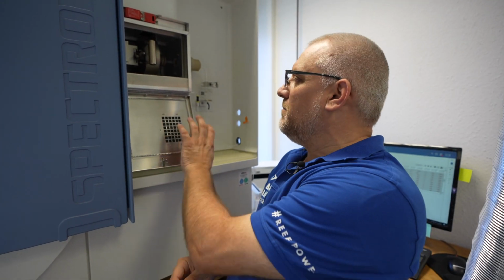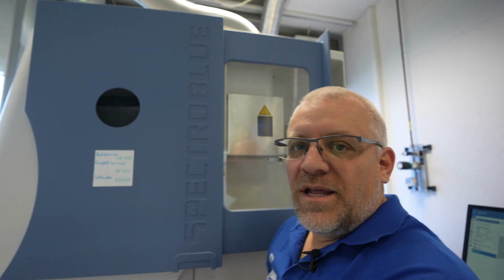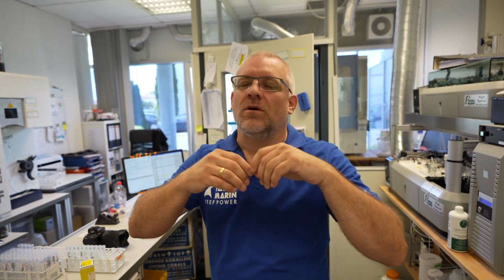The difference on this machine, so we can go to the other one and show the difference there, is that it is way more stable. We can do 100, 200, 300 tests at the same level. So if we have 100% accuracy on one specific trace element, which I really don't care about, because it doesn't matter if I have 5.1 or 5.2 zinc. What I want to know is that the metals like potassium, calcium, magnesium, sodium, which are the most important for me at the moment, and iodine and fluoride, are very accurate, and not affected by other light and by salt which is still in the reaction chamber.